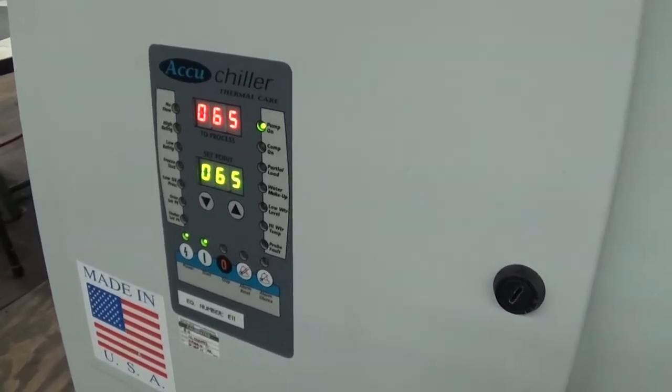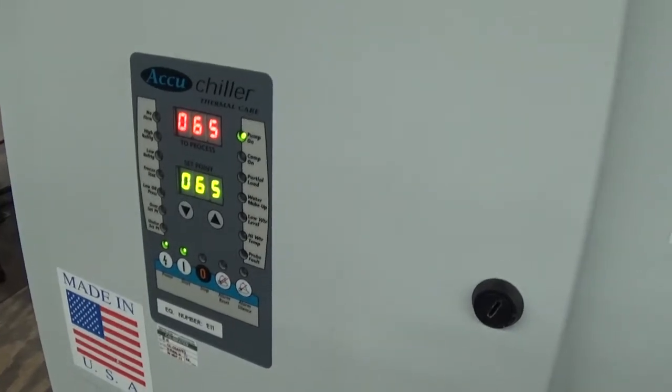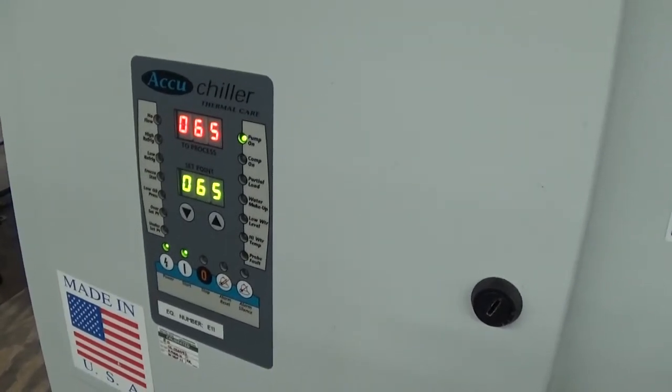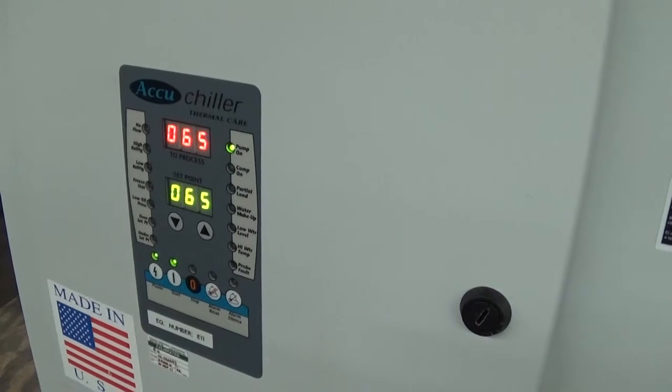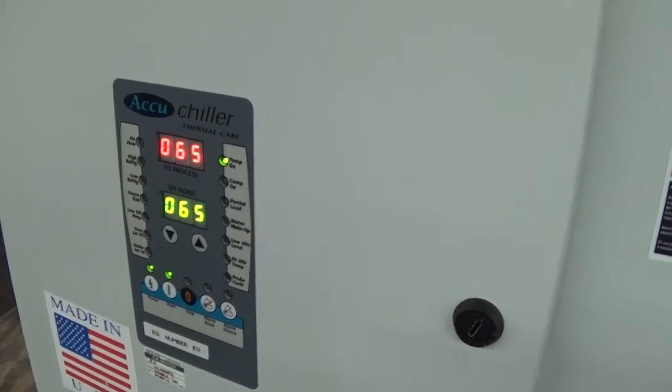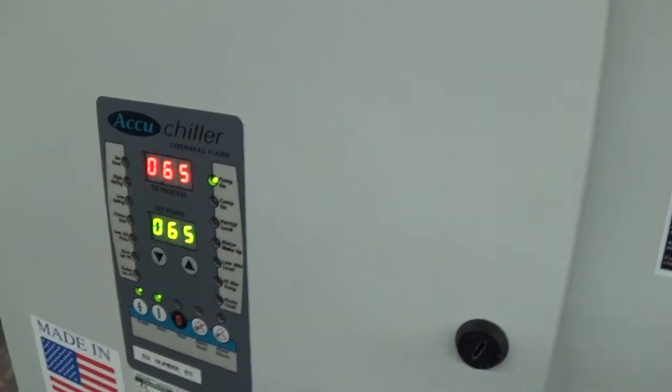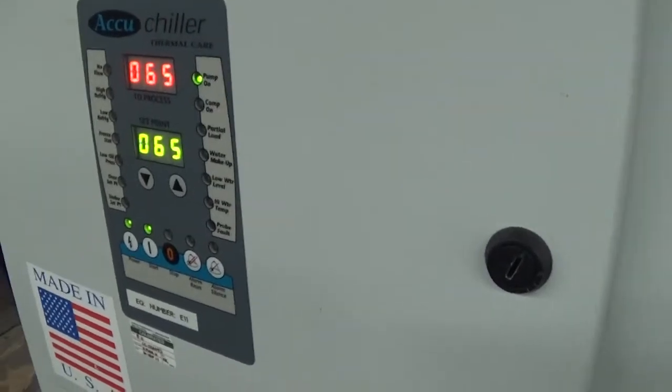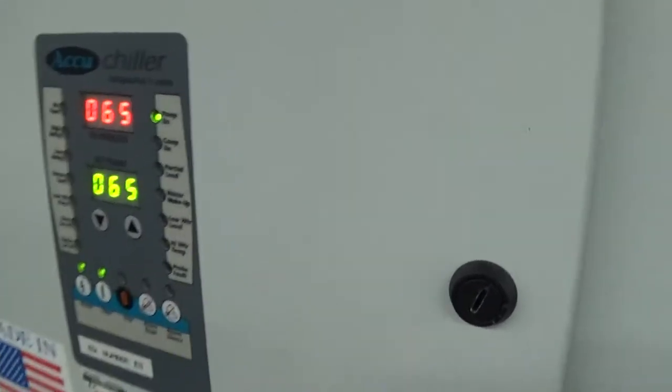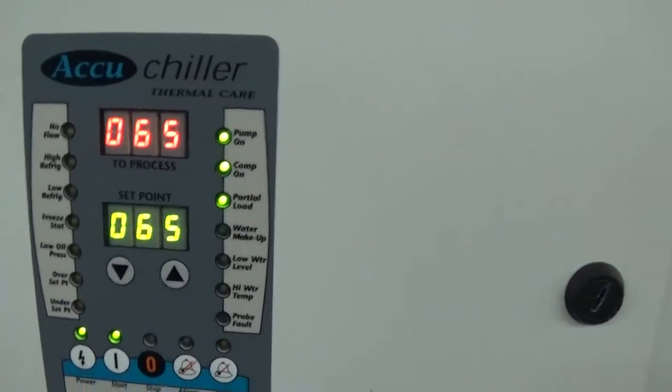We have straight water in the tank right now. To play it safe, I'm probably going to put the set point at about 48 degrees Fahrenheit so it doesn't get too cold, although the set point you can bring down as low as 30°F on this unit.